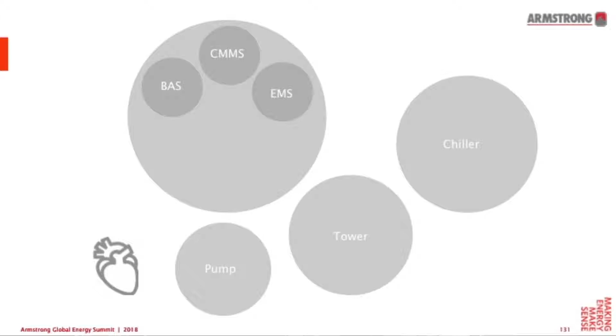When we upgrade the pump, it immediately regulates the flow in the system. Most importantly, it starts giving us information about the equipment and the health of the system. With the intelligent pump, you make all of that transparent to the building management system, whether it's the energy management system, the CMMS, or the BAS system.